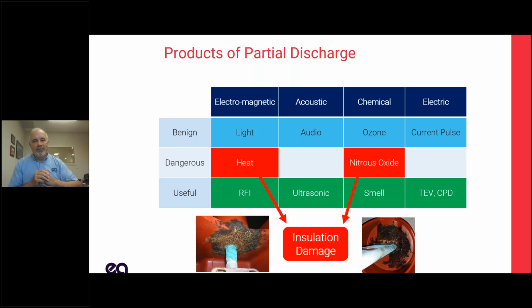Heat in the infrared spectrum, heat is good and bad. We can detect it, but it is very hot. And this is not a lot of energy in partial discharge, but there's a lot of localized heat. It's plasma. A spark is plasma, and that's going to melt a few molecules, destroy a few molecules of the insulation every time it fires. So that's happening every half cycle. You've got this happening 60 times a second for days, weeks, months, years. That is what destroys the insulation.